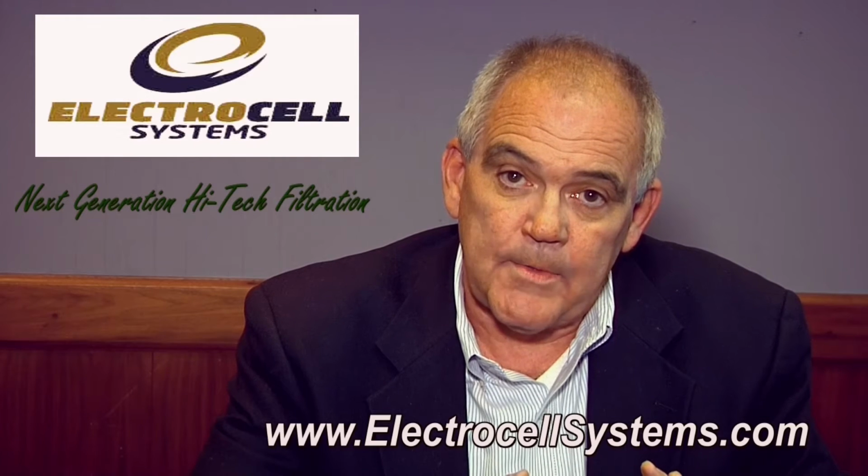What we want to do is concentrate on that 1 to 5 micron, because that is the culprit that very few systems will even touch, and that's what's costing you all the energy. The particles that are 30 to 50 microns are too heavy to stay in solution. They drop out. The tower has to be cleaned periodically. I'm not concerned with them. I'm concerned with the small particles that accumulate over time and cost you all the energy.